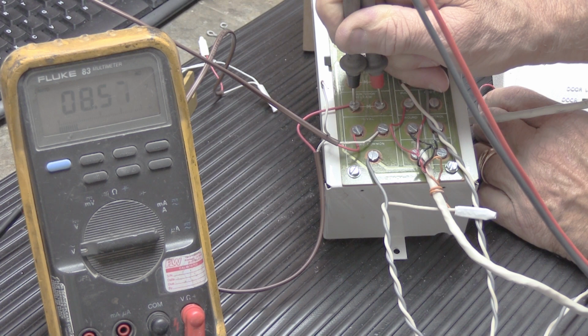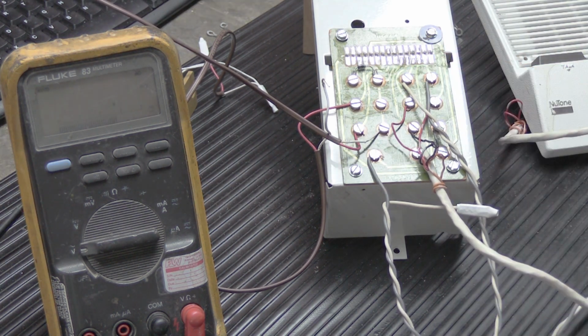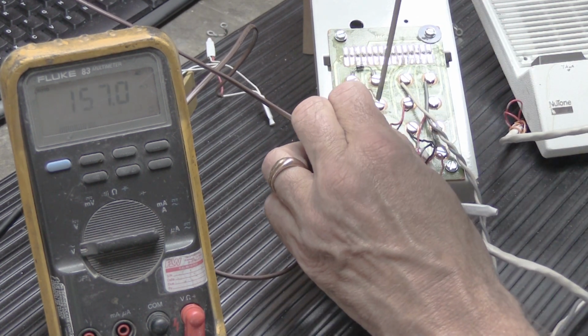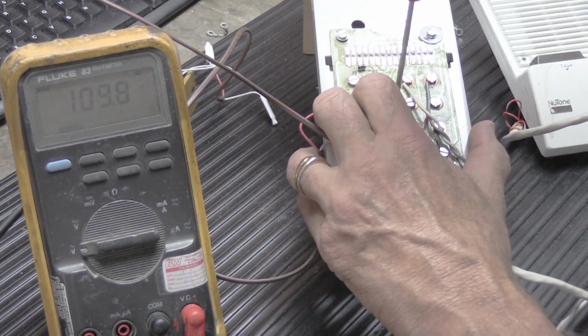And that would be fine. So that indicates that the circuitry in the 478 control amplifier is fine. If you still get virtually 0 volts, then there's a problem with your 478 and it needs to be repaired. Now what we're going to do is reattach the white wire to the terminal for the main door release, so it's back like it was.